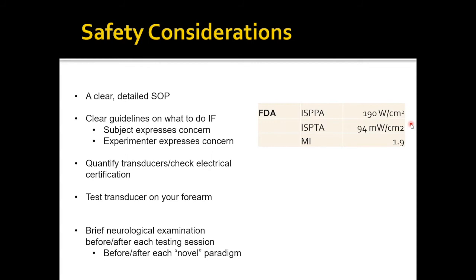Something we do in Professor Chen's and Professor Lozano's labs is test the transducer on our own forearms. That's a good way to gauge whether your coupling is adequate and whether the intensities will be tolerable for a subject, especially with a new paradigm like minutes of sonication. If your forearm feels hot or warm, the subject will probably feel hot or warm on their scalp too, so something needs to change.